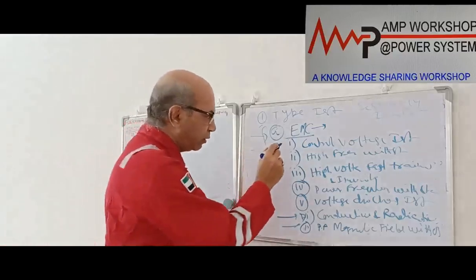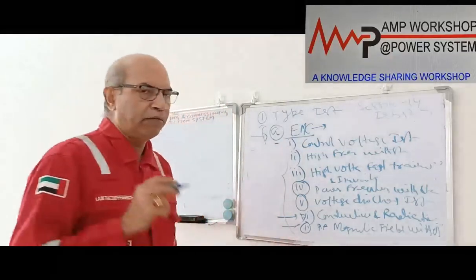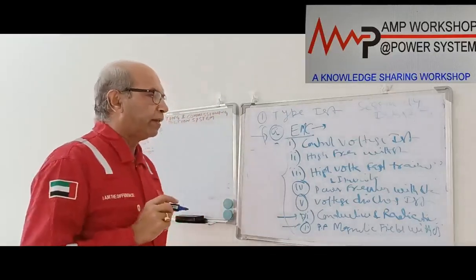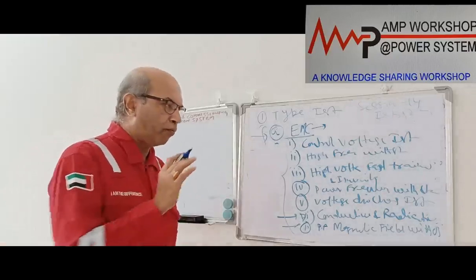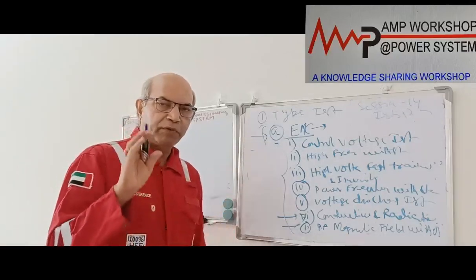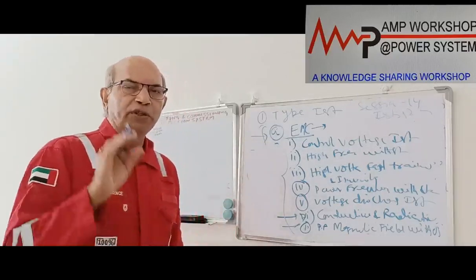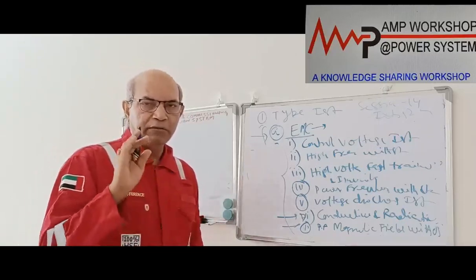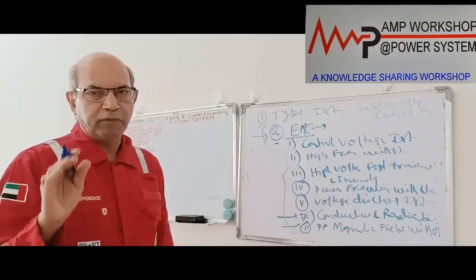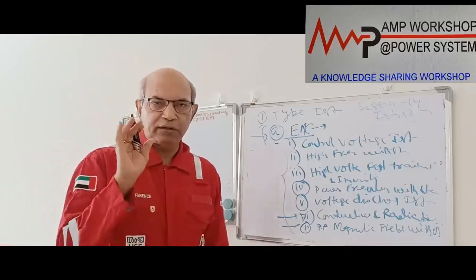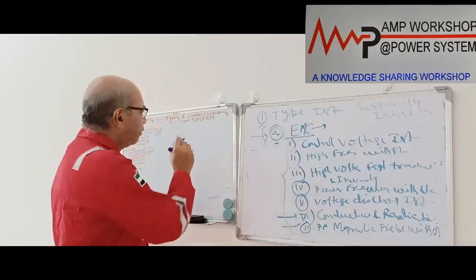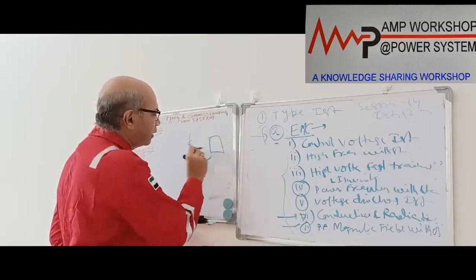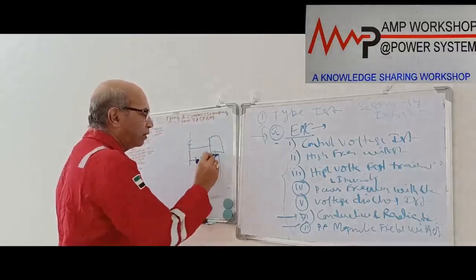For all these tests, one of the things to ensure the protection device is maintaining its performance is that for most of the tests we keep the protection device in operation with the CT, PT supply at 90% supply voltage. These are the two main inputs coming to the relay, right? The CT supply and PT supply. These two inputs will decide the relay operation, and the control supply.